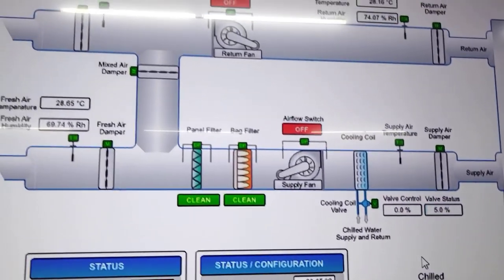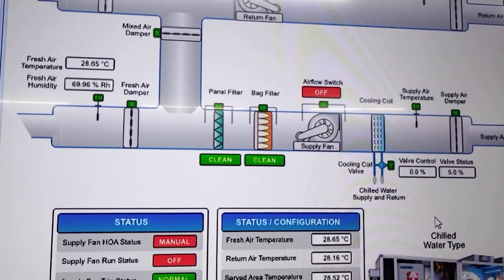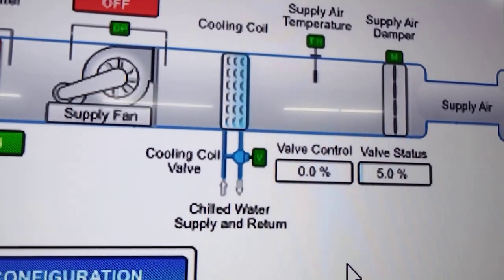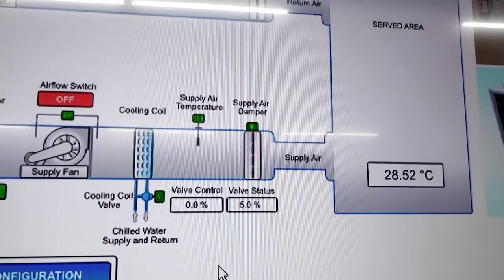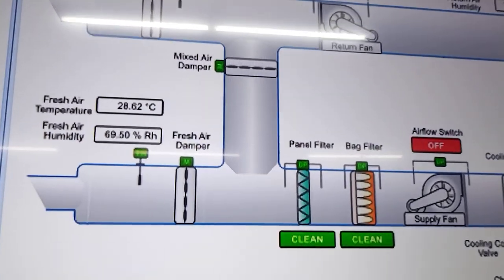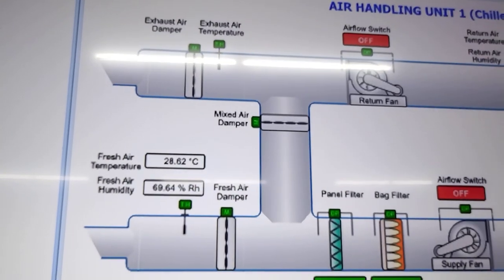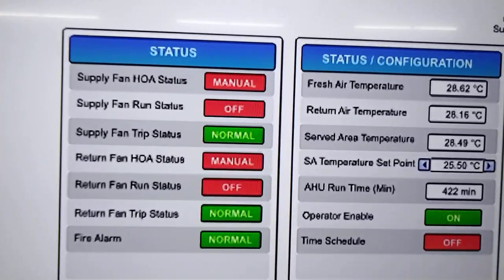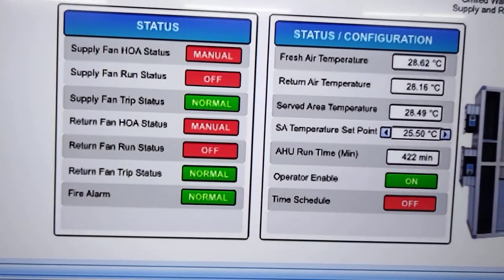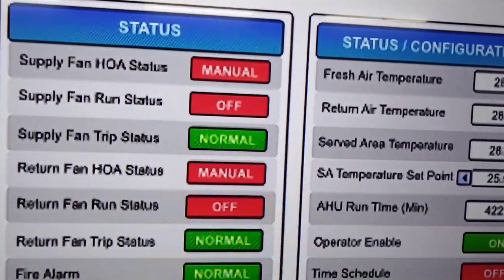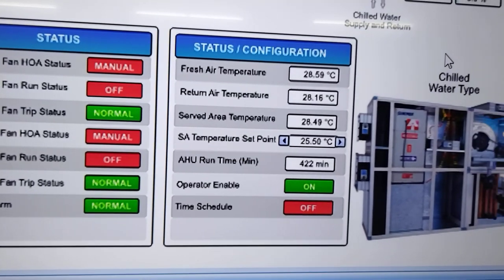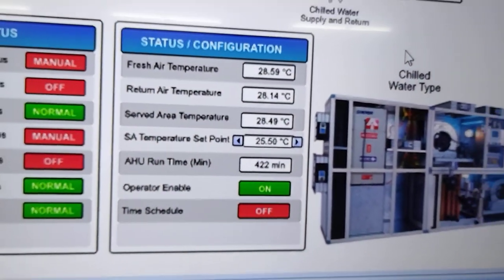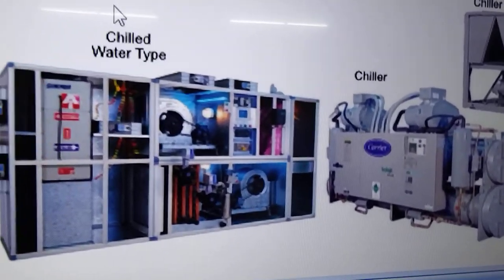These are the typical components of an air handling unit. We have the supply fan, return fan, the filters — pre-filters and bag filters. Then we have our cooling coil with the valve actuator. Then we have the supply and return dampers, our mixed air damper, fresh air damper, and exhaust air damper. Down below we have information coming from our motor control — right now it is in manual position. The selector switch supply fan run status is off, trip is normal, then fire alarm, temperature information.